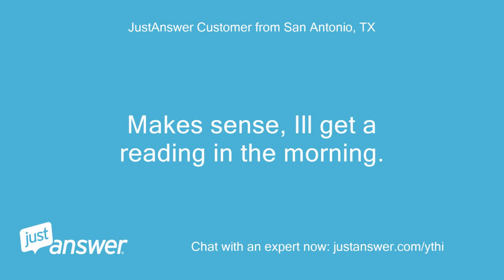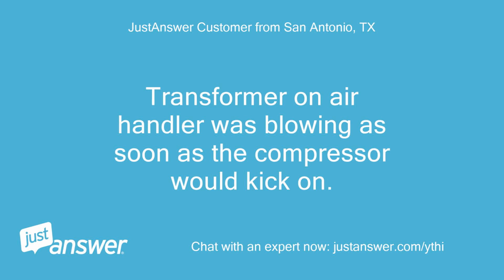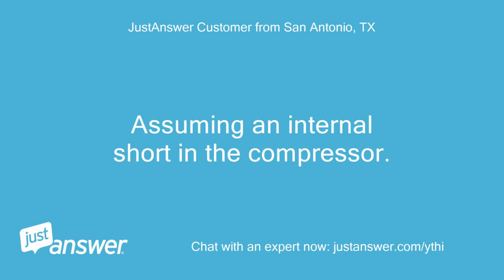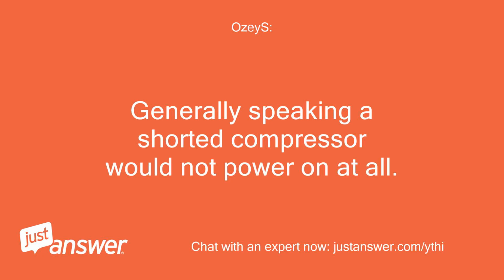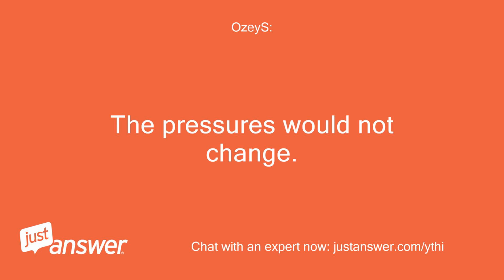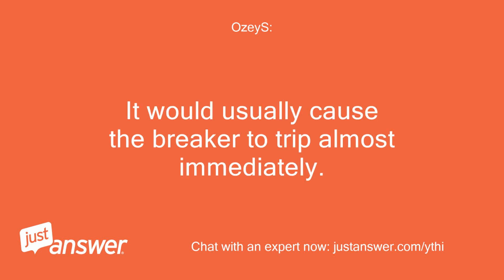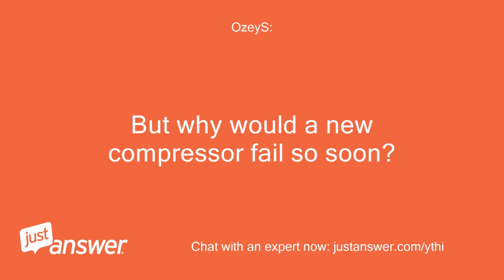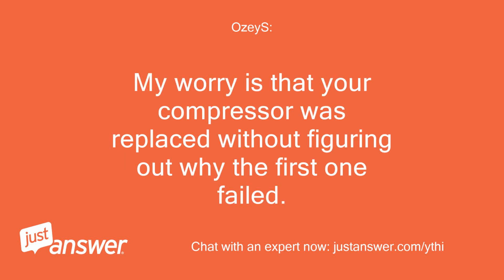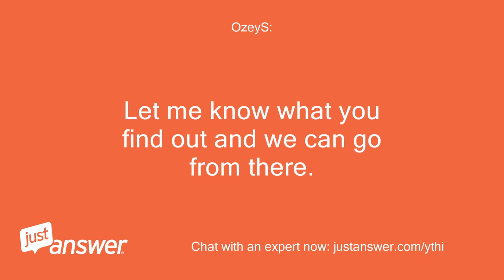Makes sense, I'll get a reading in the morning. Transformer on air handler was blowing as soon as the compressor would kick on. Assuming an internal short in the compressor. Generally speaking, a shorted compressor would not power on at all. The pressures would not change. It would usually cause the breaker to trip almost immediately. But why would a new compressor fail so soon? My worry is that your compressor was replaced without figuring out why the first one failed. Let me know what you find out and we can go from there.